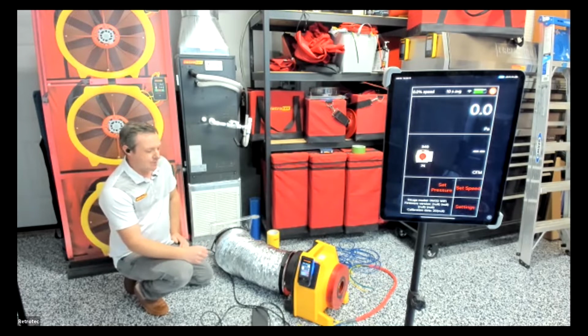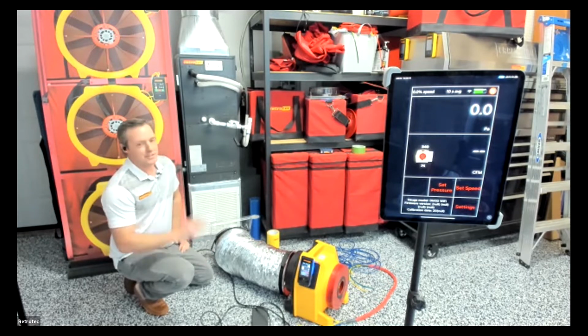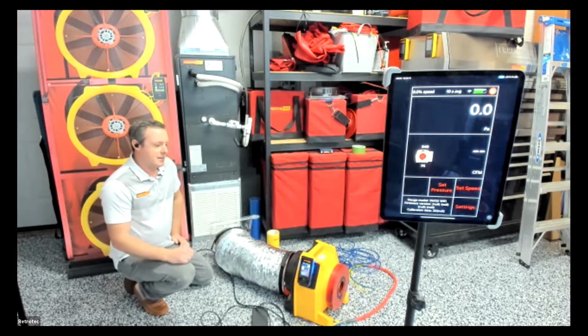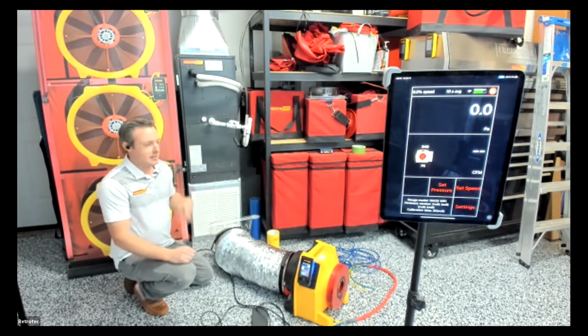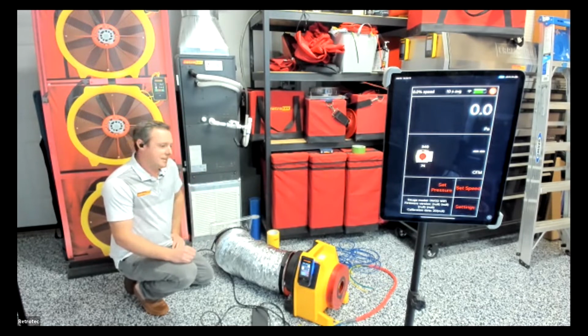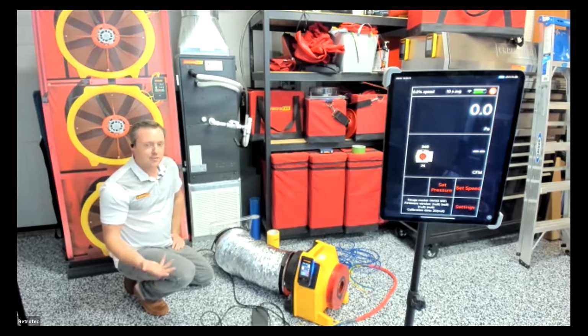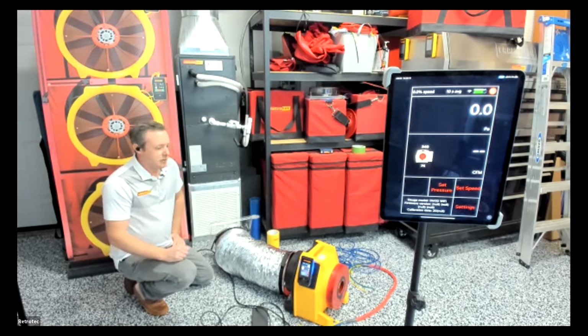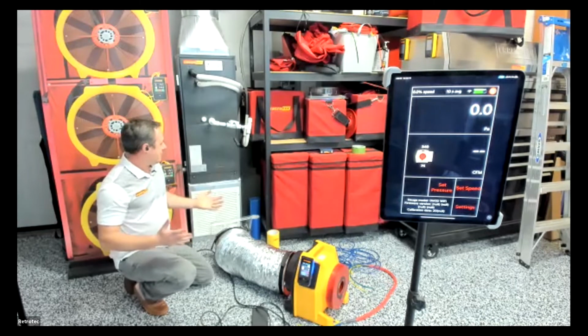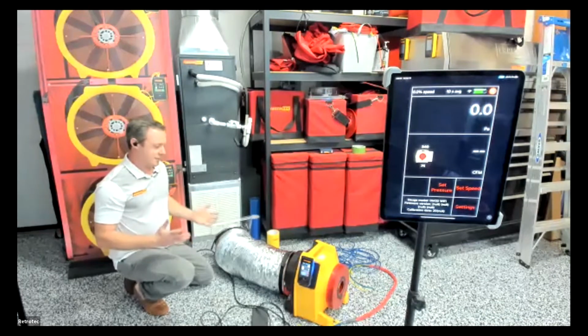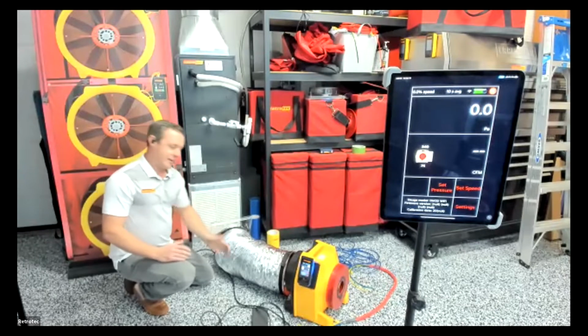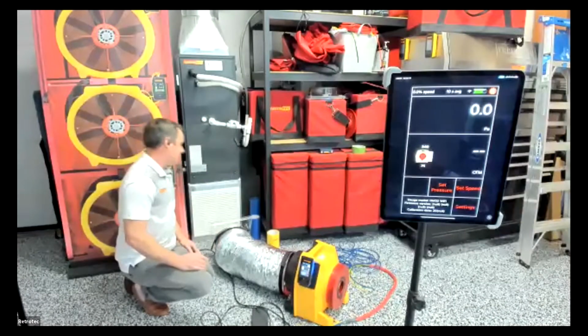Anything that's going to manipulate pressure inside of that duct system, we want to make sure that's not going to kick on. If it has a fan cycler switch that runs ventilation a certain number of hours a day, we want to make sure that's not going to come on during the test. If there's a ventilating dehumidifier or something like that hooked up to the duct system, we want to make sure that's not going to turn on as well. So we want nothing going on inside of that duct. The only thing we want to see moving is air generated by the duct tester fan here.